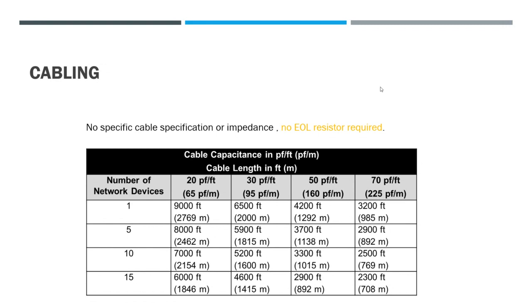HART's spec is technically 230 to 1100 ohms, but 250 is what we use since it works well for the math. As for the communication wire spec, does HART require shielded twisted pair, or is there a different standard? For HART, there's no specific cable specification or impedance. Industry standard is shielded twisted pair in the field, and you can use unshielded twisted pair in controlled environments like the control room where there isn't much EMF.